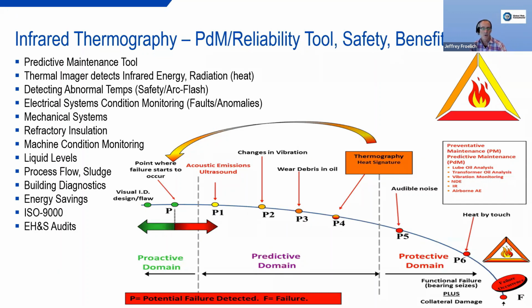What I'm showing here on the graphical display is what's known as the PF curve, the potential failure curve. It's basically just a way of representing an asset's behavior or condition before it reaches its failure mode. It illustrates an asset's progression towards failure. So what we're trying to do is use the technology to predict and forecast, through temperature measurements, potential unusual circumstances, such as imbalanced loads, loose connections, deteriorated connections, overloaded circuits. The graph will help display the health of equipment over time. The idea is, if you wait too long, you get to the protective domain, which is too late. You start hearing mechanical chatter or electrical noise, and you have heat to a point of imminent failure.